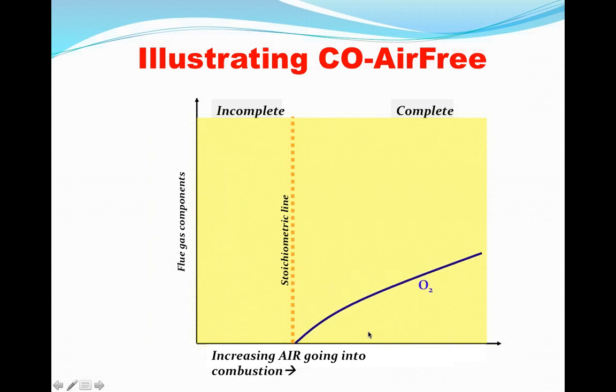So here's the oxygen line. If you had the ability to dial the air concentration going into combustion and increase it from a low value to a higher value, you would eventually see residual oxygen in the flue gas. These numbers up here would be the numbers displayed in your flue gas analyzer. As you dialed in more air, you'd see more oxygen, because you're introducing more air into the system. At this point, you had air still coming into the system, but there wasn't enough air to go around, so you're using up all the air and you had no residual or excess air. So this is the excess air line.